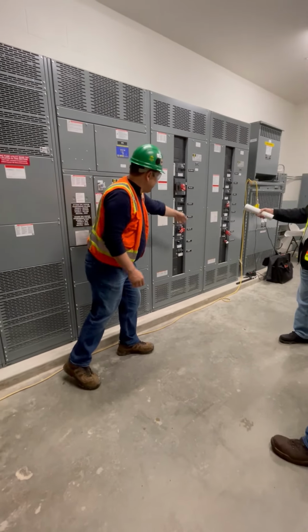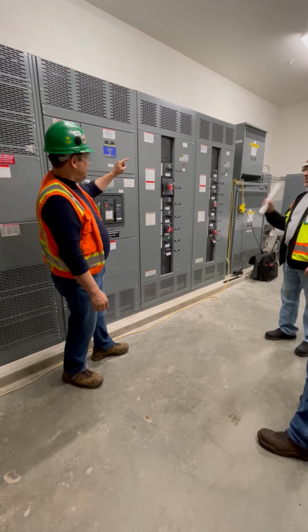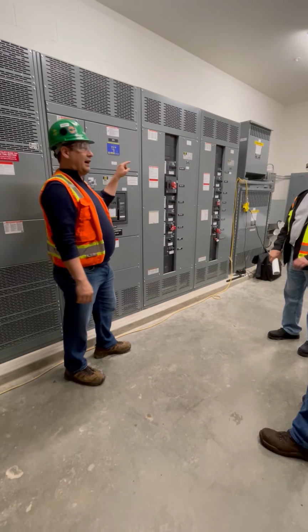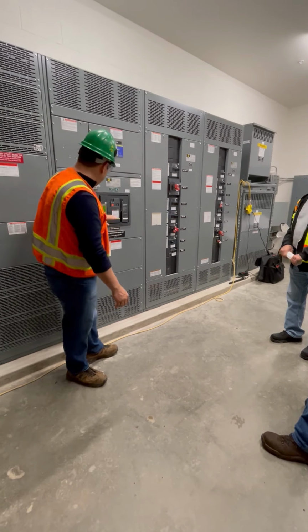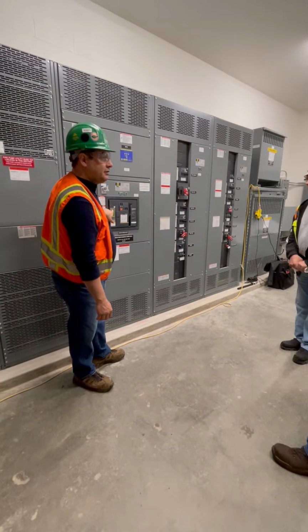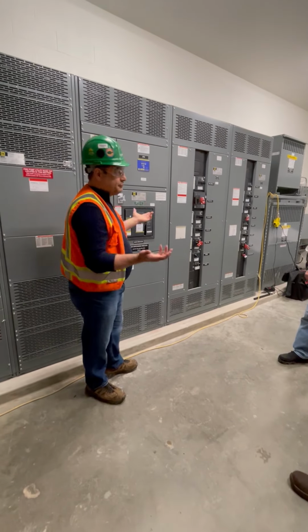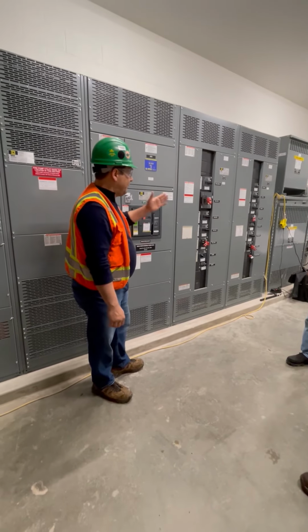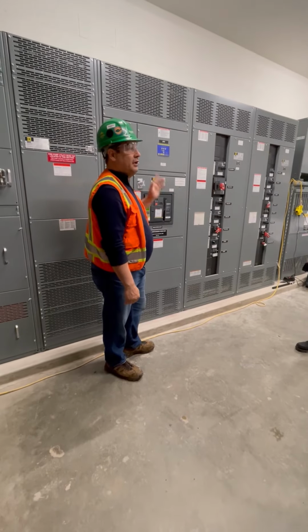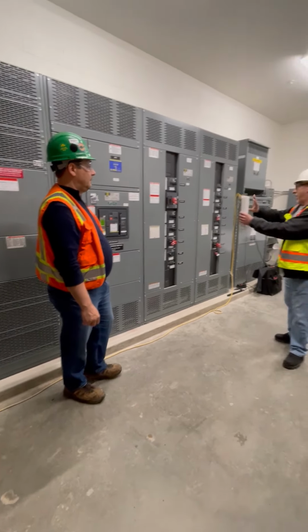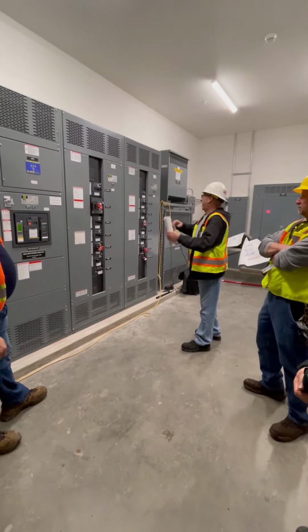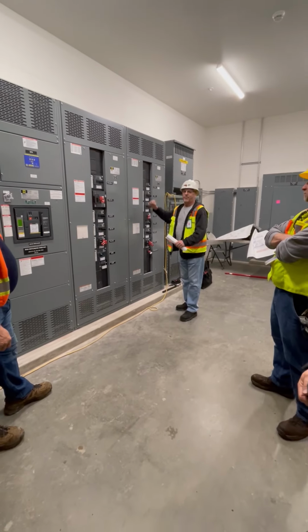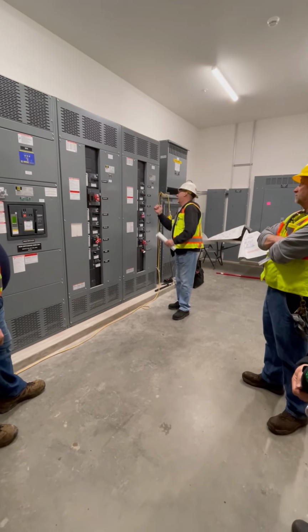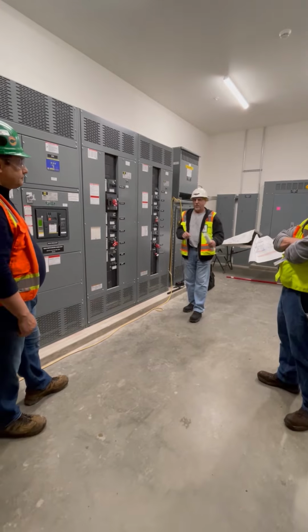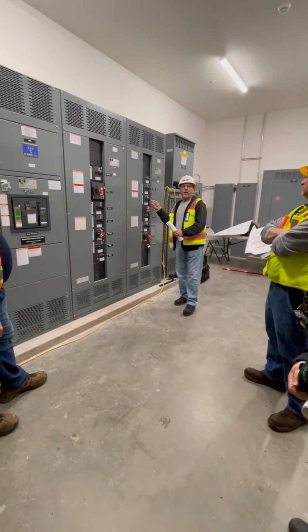You turn all these feeders off, turn this one on, and start one by one. Process of elimination, right? Yep. So if the LED comes on ground fault, that's something you may want to think about, and then try to figure out where the feeder is. It's the same thing at Fisher's Landing. Like I said, we had to turn everything off downstream, turn it back on one at a time, wait two minutes, and then eventually, boom, that's the one.